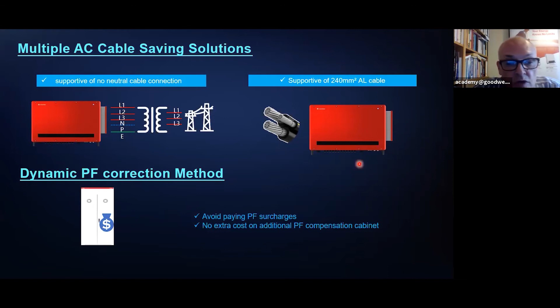Now, of course, when a building is such as a factory with lots of motors in it or something like that, it can have highly reactive loads. So in order to compensate for that, you'd need to buy some power factor correction cabinets to avoid the surcharges that the grid companies may impose upon you. Obviously you don't want to do that, but you don't necessarily need to buy a power factor correction cabinet. You can use the function within the inverter itself to apply that correction between -0.8 and +0.8. So we do have that ability as well within our equipment.